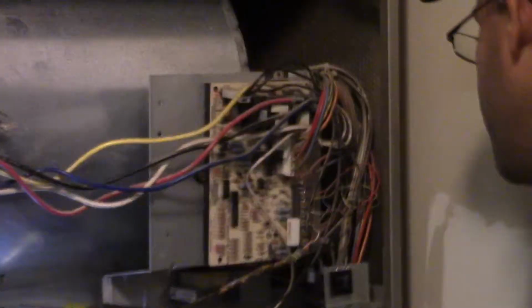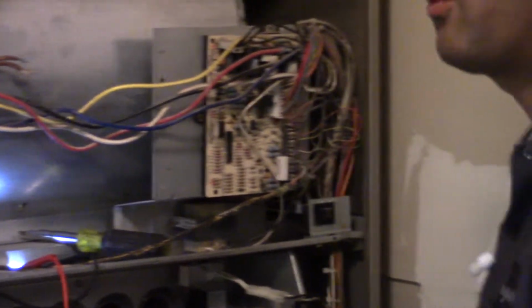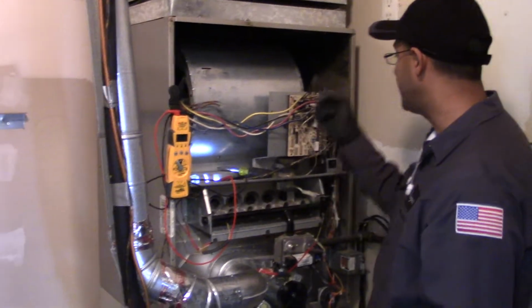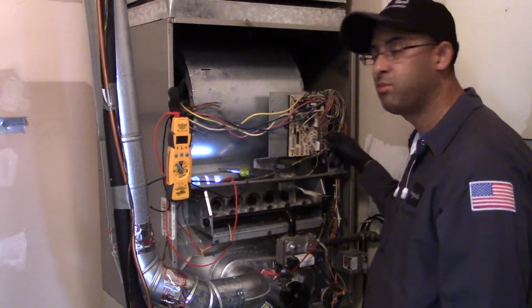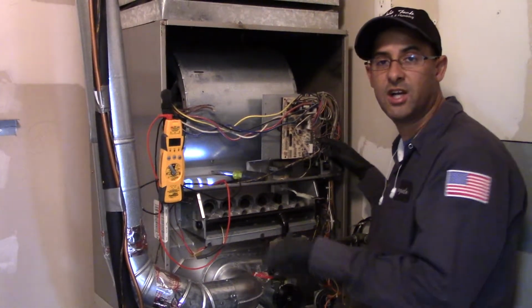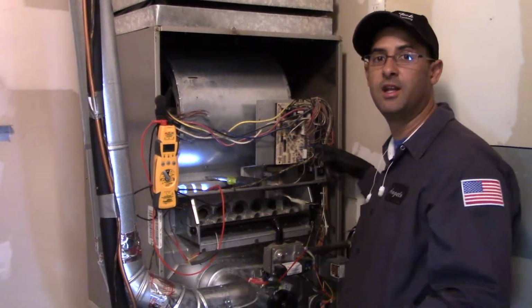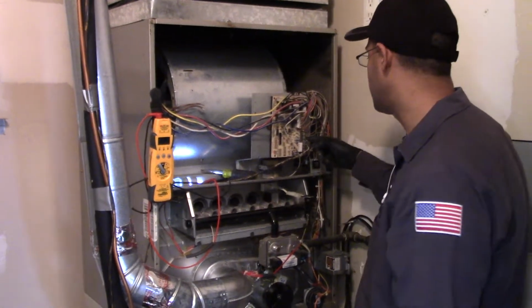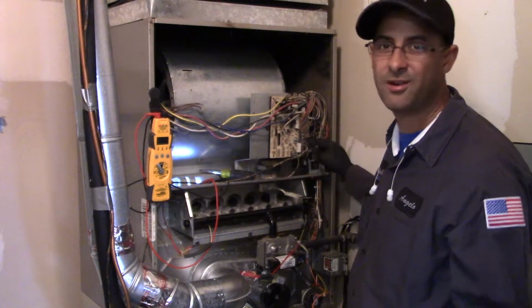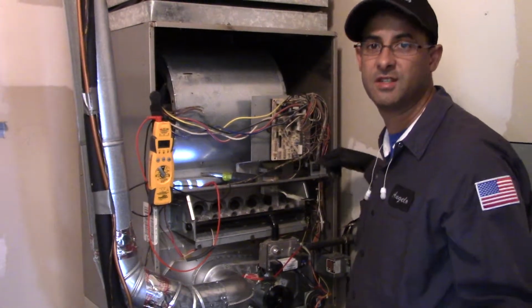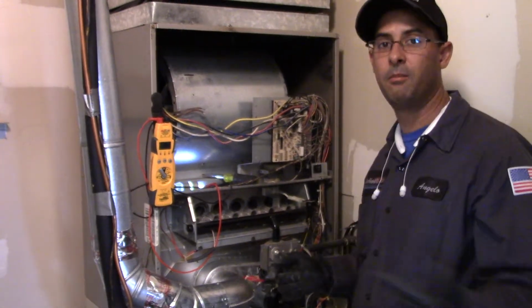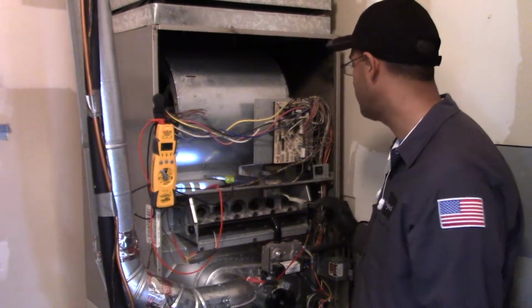So all those other wires like the Y, the W, the G are basically the red wire, but it's sending it back through the thermostat, and when it gets to this board and gets that terminal, that's when it energizes either the cooling or the heating or the fan. So it's good to know that the thermostat is just a temperature switch. It's just allowing that red wire to come back to a certain place on that board.